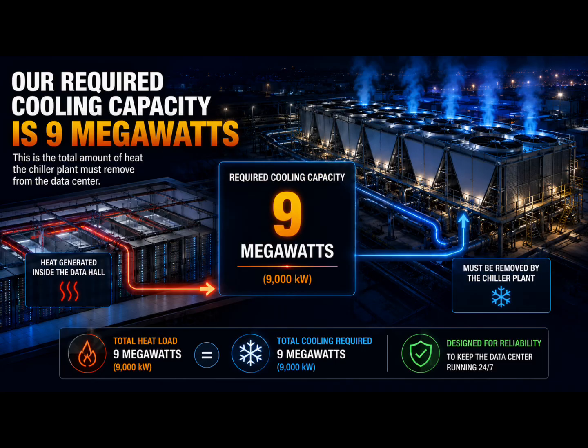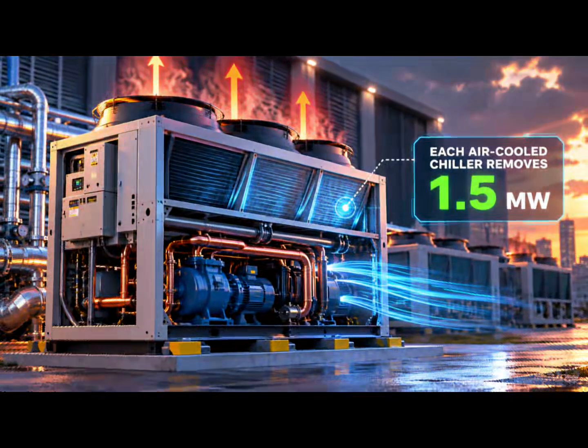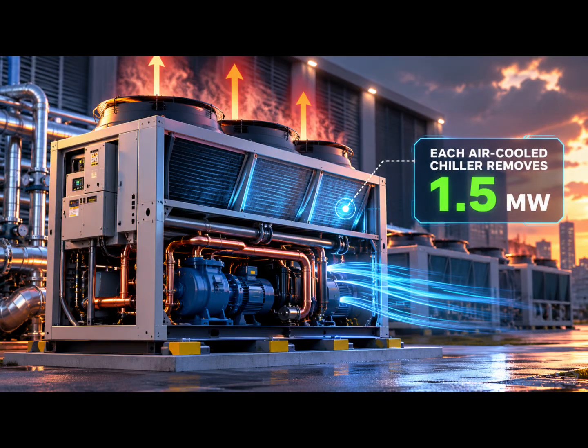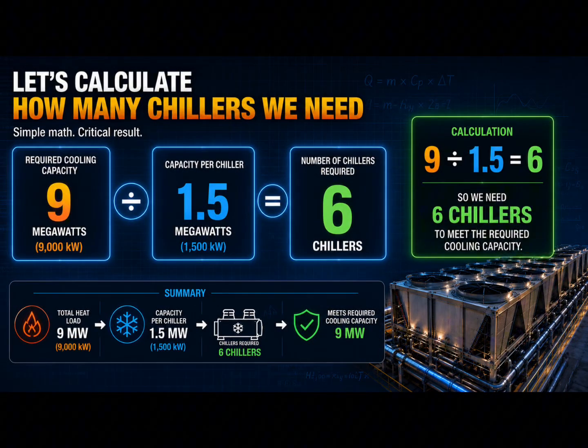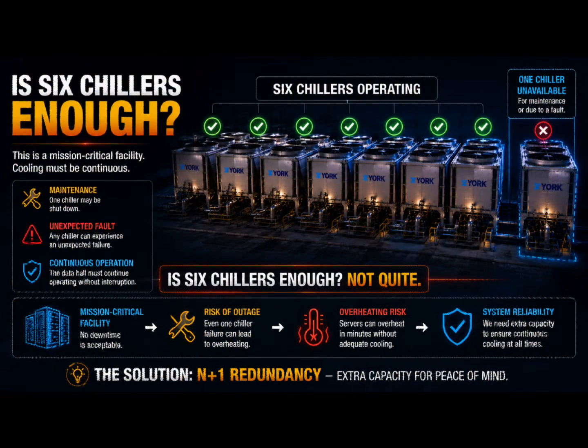For our project, our required cooling capacity is 9 megawatts. Each air-cooled chiller can remove 1.5 megawatts. Let's calculate how many chillers we need. 9 divided by 1.5 equals 6. So, is our answer 6 chillers?